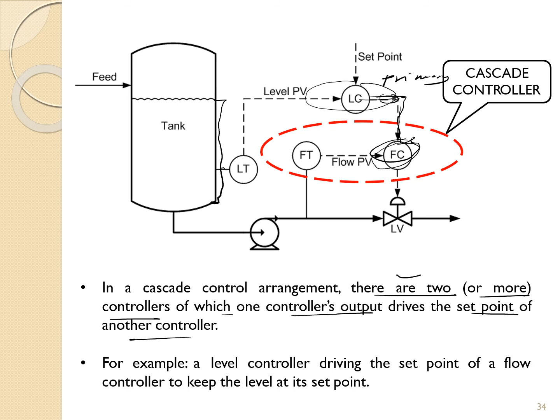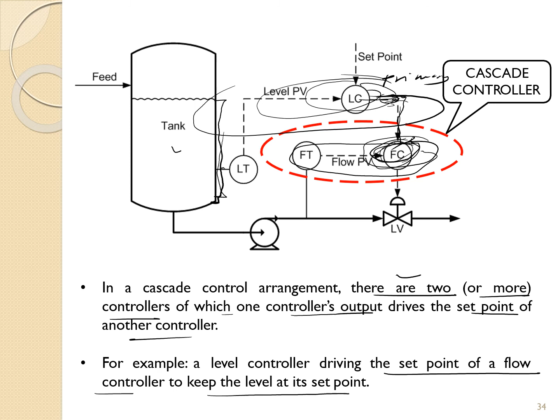For example, a level controller driving the set point of a flow controller to keep the level at its set point. So this level controller drives the set point of this flow controller to keep the level in here at its set point. The main objective is still the level of the tank, but to fulfill this control objective, we need two controllers, our primary control and also secondary control. The flow control in turn drives a control valve to match the flow with the set point the level controller is requesting. So the secondary controller, which is the flow controller, drives a control valve. It will adjust the control valve with the set point given by the level controller.